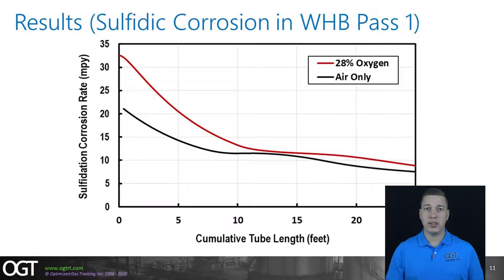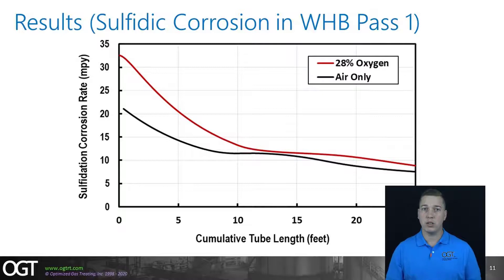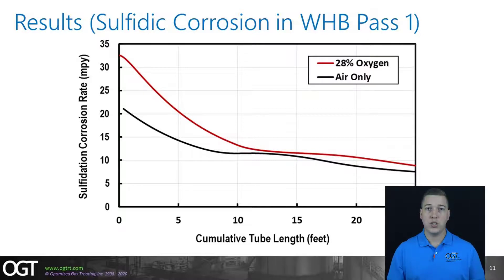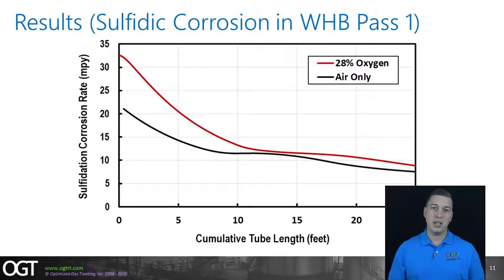This next graph shows the same two cases — base case air-only versus 28% oxygen enrichment — but this time looking at sulfidation corrosion rates in mils per year along the length of the boiler tubes. It becomes even more apparent that something is going on with this particular waste heat boiler. The peak corrosion rate for base case air-only operations is around 21 mils per year based on the Couper-Gorman curves — already twice the recommended maximum corrosion rate of 10 mils per year. As oxygen enrichment is added, this problem is compounded, pushing the corrosion rate up to 33 mils per year — three times the recommended limit. This represents a 50% increase in corrosion rate just by adding low-level oxygen enrichment to an already borderline plant.